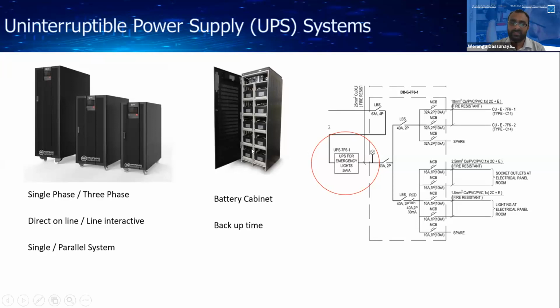So we are mainly using 3 types of UPSs. The first one is direct online or line interactive. There may be single phase or 3-phase distribution, single phase or 3-phase UPSs. Or we can use a single UPS or a parallel system. That means if we cannot cater the power from a single UPS, we have to parallel 2 UPSs and keep the power.